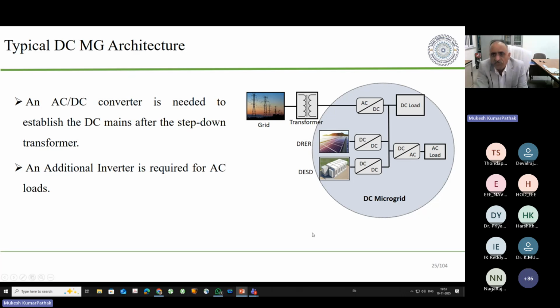How will this change if you have a solid state transformer? If instead of the conventional transformer you apply a solid state transformer here, the output would be DC. So this converter is no longer required, because you can use the DC link of the solid state transformer directly. Similarly, if you want to supply an AC load, that converter will not be required either; you can use the AC output directly.